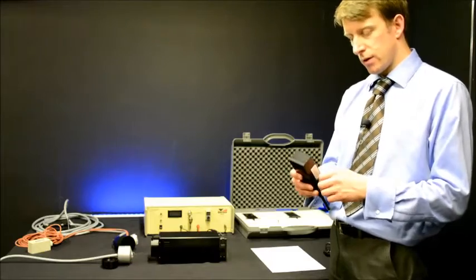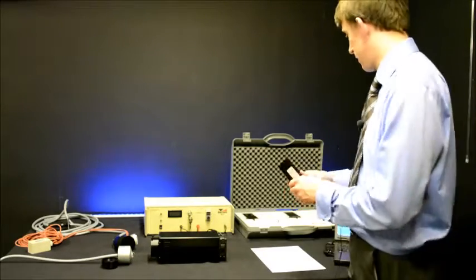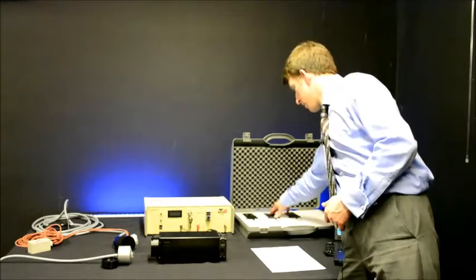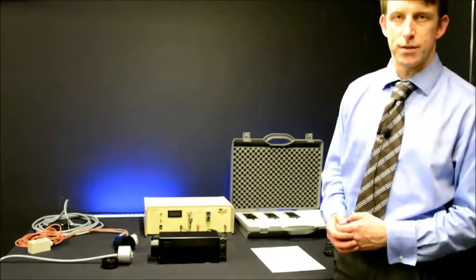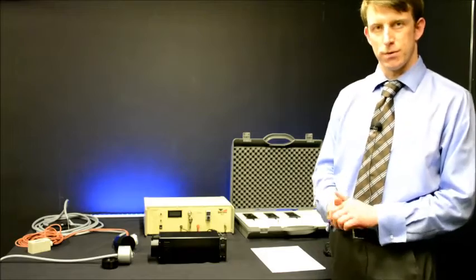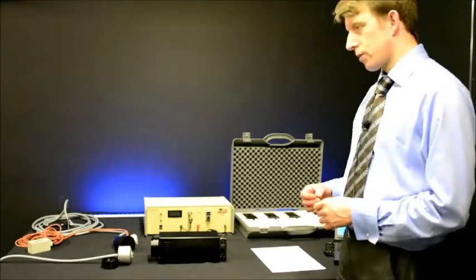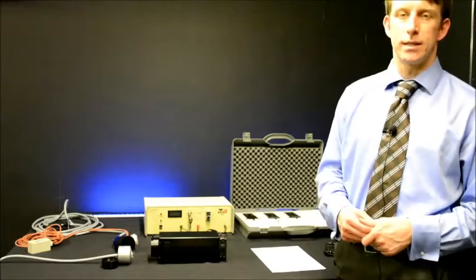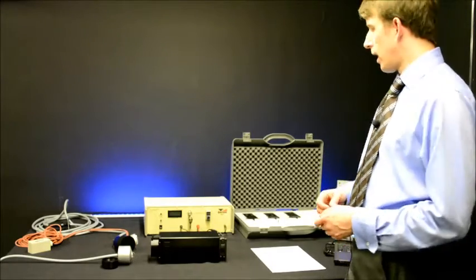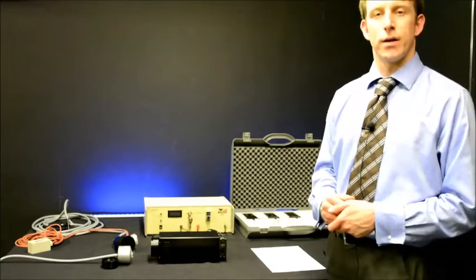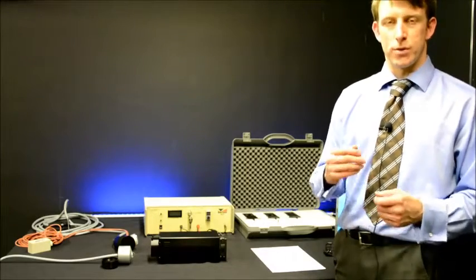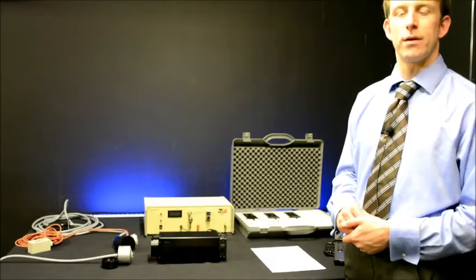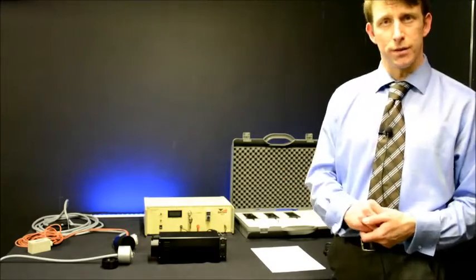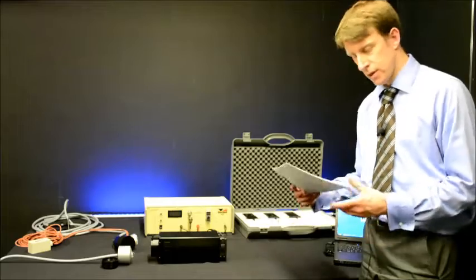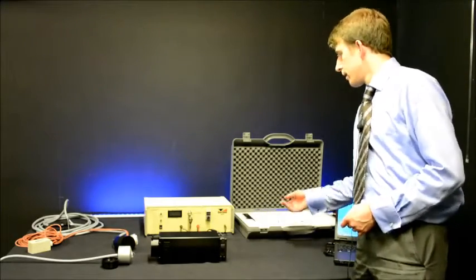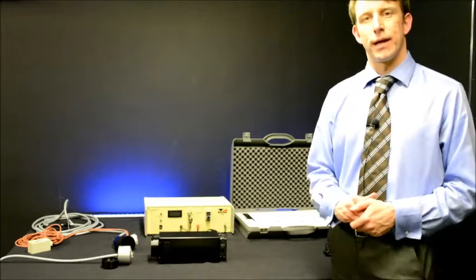Kilowatt lamps tend to be used as the principal reference lamp for calibrations of spectral radiometers intended for use in solar irradiance measurements. These are typically used, or certainly need to be, calibrated in a dark room, a dark environment. The input optic should be set to the correct distance at which the irradiance of the kilowatt lamp is known and reported in the associated calibration certificate provided, and one can thereby calibrate the system.